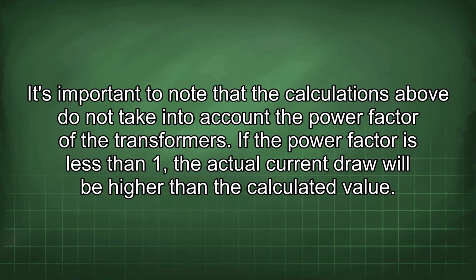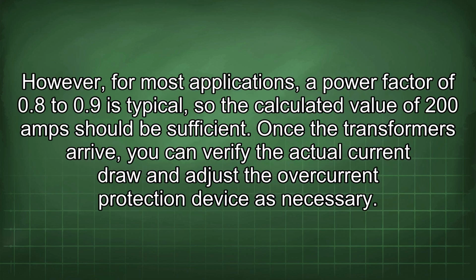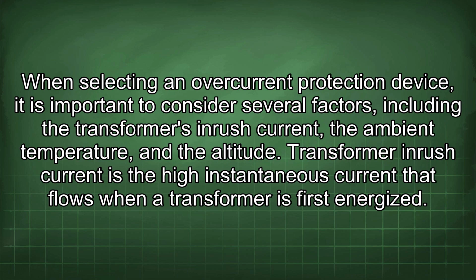It's important to note that the calculations above do not take into account the power factor of the transformers. If the power factor is less than 1, the actual current draw will be higher than the calculated value. However, for most applications, a power factor of 0.8 to 0.9 is typical, so the calculated value of 200 amps should be sufficient. Once the transformers arrive, you can verify the actual current draw and adjust the overcurrent protection device as necessary. When selecting an overcurrent protection device, it is important to consider several factors, including the transformer's inrush current, the ambient temperature, and the altitude.